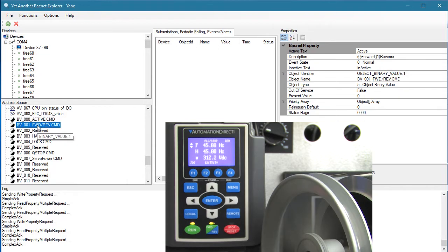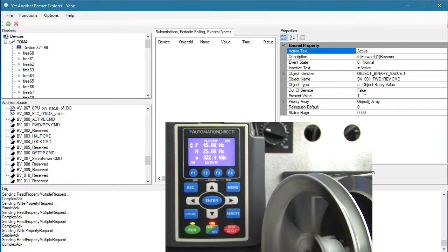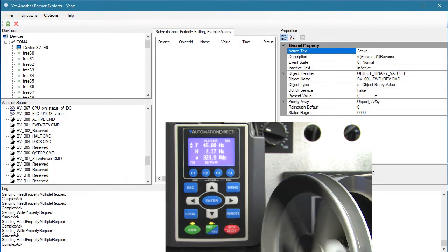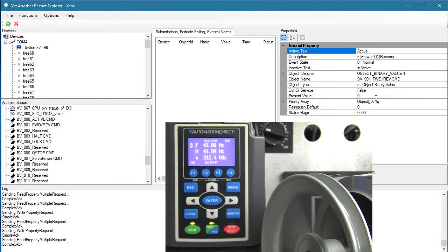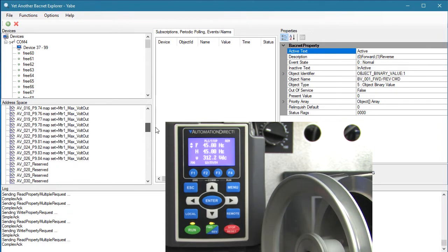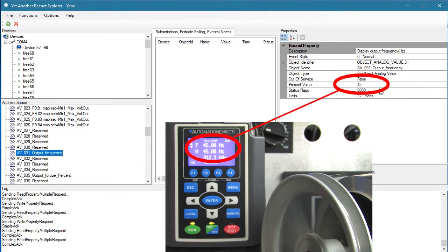Binary value 1 is the direction, so entering a 1 reverses the direction of the motor. Setting it back to 0 changes it back to the forward direction. Analog value 31 displays the current frequency of the drive — sure enough, we see it is running at 45 Hz.